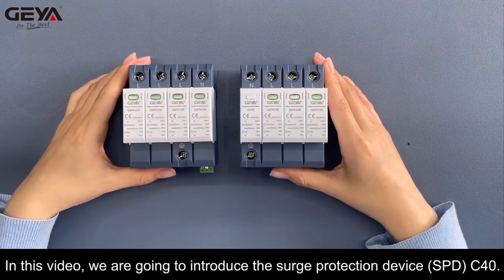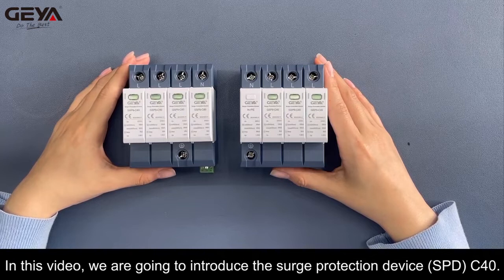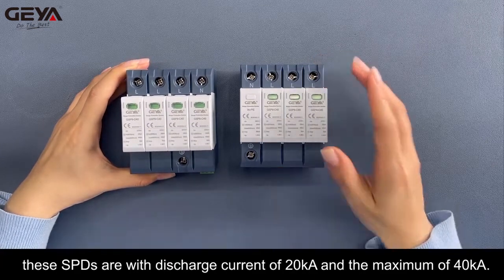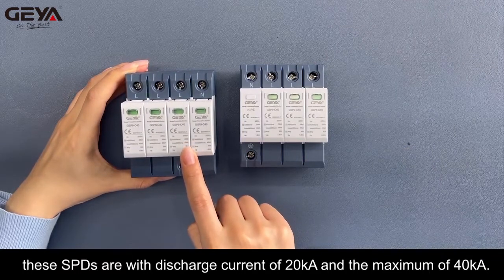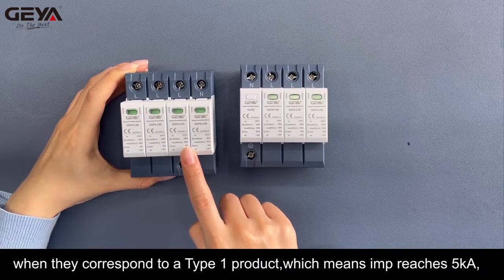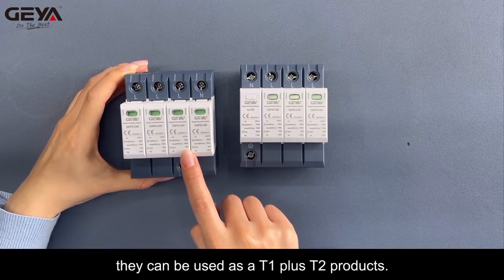In this video, we are going to introduce the Surge Protection Device, SPD-C40. In the case of an 8/20 waveform of Class II, these SPDs have a discharge current of 20KA and a maximum of 40KA. When they correspond to a type 1 product, which means Iimp reaches 5KA, they can be used as T1 plus T2 products.